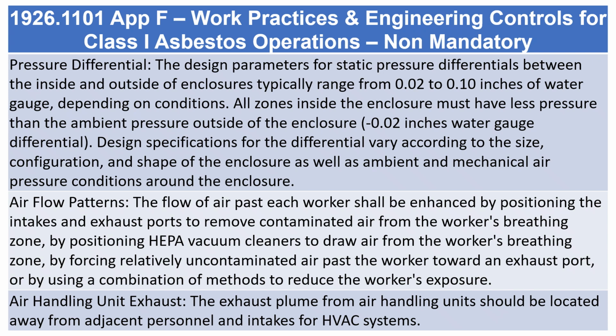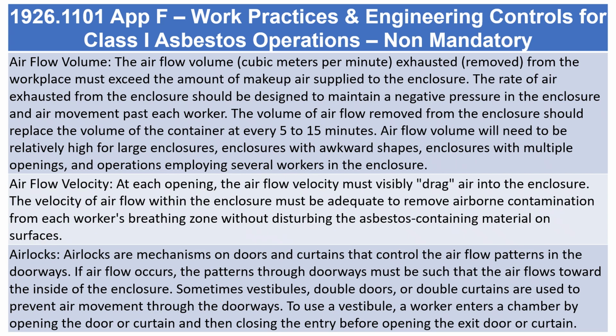Airflow patterns. The flow of air past each worker shall be enhanced by positioning the intakes and exhaust ports to remove contaminated air from the worker's breathing zone, by positioning HEPA vacuum cleaners to draw air from the worker's breathing zone, by forcing relatively uncontaminated air past the worker toward an exhaust port, or by using a combination of methods to reduce the worker's exposure. Air handling unit exhaust. The exhaust plume from air handling units should be located away from adjacent personnel and intakes for HVAC systems.